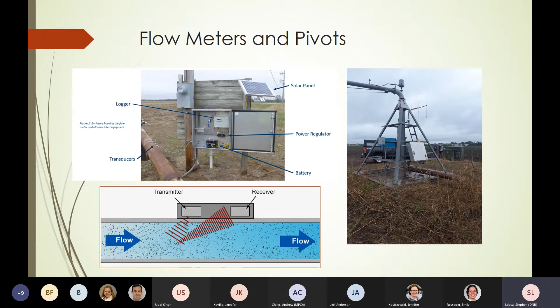A difference between stream gauging equipment versus what we're using now: stream gauging equipment, like this Stream Pro on the left, uses a Doppler effect to bounce noise off particles and return that to the instrument to measure a frequency change. But ultrasonic meters send signals into the pipe, timed by the downstream receiver, and it collects these signals and spits out numbers that make sense to water scientists.